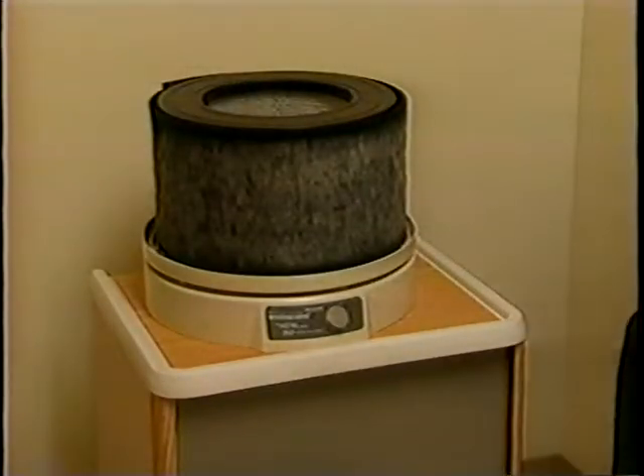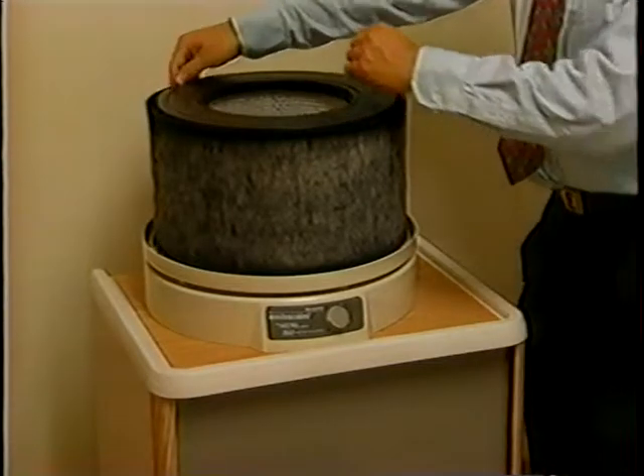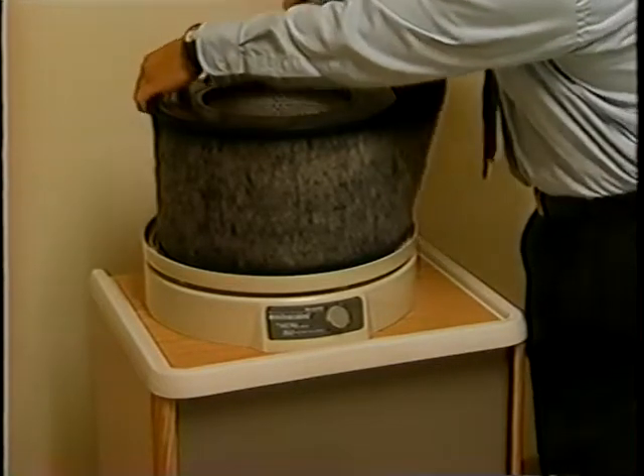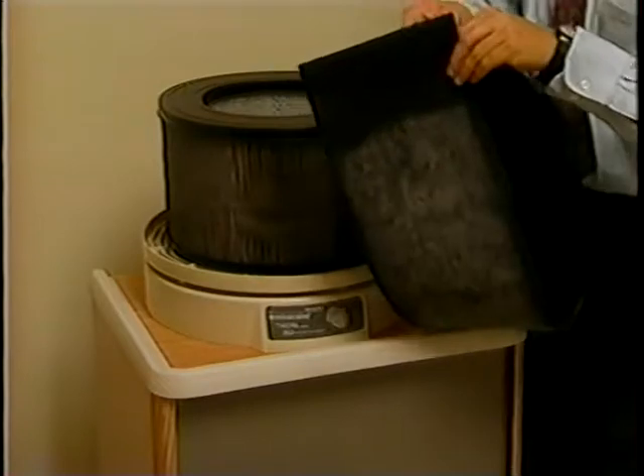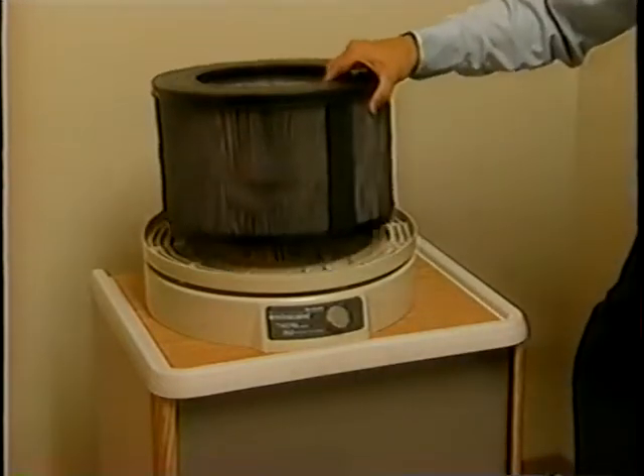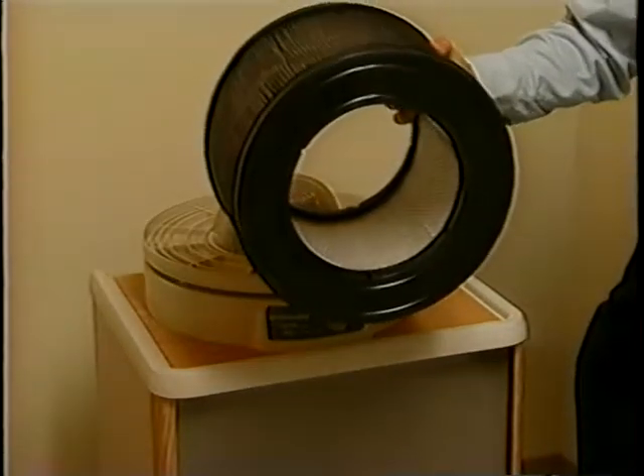HEPA filter units require very little maintenance. You should check the manual that comes with the unit, but in general, the pre-filter should be changed every 6 months, and the final HEPA filter should be changed every 1 or 2 years. Make sure that you change the filters and dispose of them in accordance with local requirements. In some areas, you may be required to wear respirators when changing the filters, and also to treat the discarded filters as medical waste. That's it for isolation room ventilation. Let's move on to negative pressure.